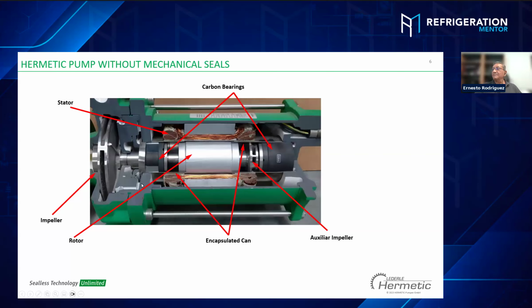We have the cutaway of the pump. We have the stator, and the fluid lubricates the carbon bearings. We use carbon bearings for this application because we use hydrostatic suspension, meaning the same refrigerant is going to maintain and lubricate. It's like what happens with the internal combustion motor. You have the crankshaft, you have the oil, and the bearings maintain the crankshaft suspended by hydrostatic fluid. This is exactly the same principle, okay?